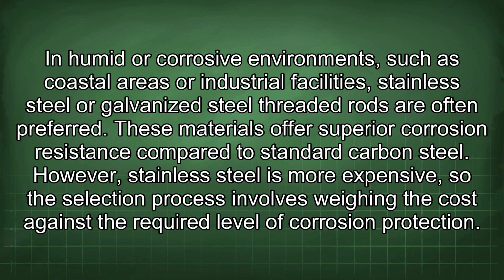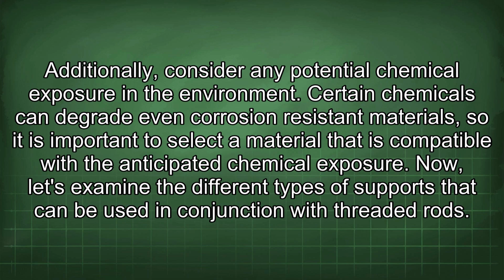These materials offer superior corrosion resistance compared to standard carbon steel. However, stainless steel is more expensive, so the selection process involves weighing the cost against the required level of corrosion protection. Additionally, consider any potential chemical exposure in the environment. Certain chemicals can degrade even corrosion-resistant materials, so it is important to select a material that is compatible with the anticipated chemical exposure. Now, let's examine the different types of supports that can be used in conjunction with threaded rods.